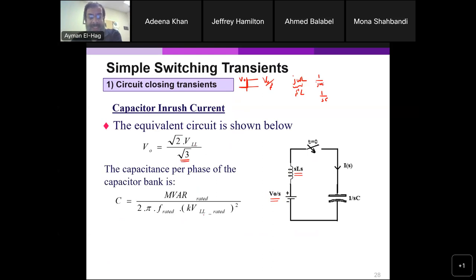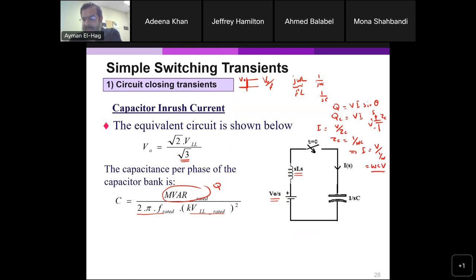Now, the value of the capacitance C is the MVAR rating, or the Q of the capacitors, over 2 pi F times V squared. From where do we get this relationship? We know that Q is equal to VI sine theta. For the capacitor, QC is equal to V times I. With a capacitor ZC, current I and voltage V, I is equal to V divided by ZC. ZC itself is 1 over omega C as a magnitude, so I equals omega C times V. Your QC will equal V times I, or omega C times V squared. So your C is equal to QC divided by omega V squared, and omega is 2 pi F. And that's exactly what you see here.